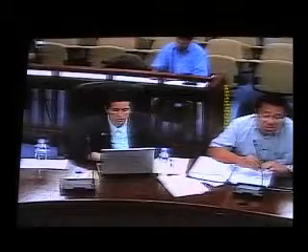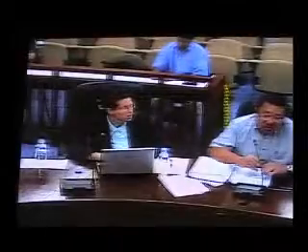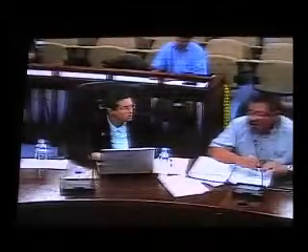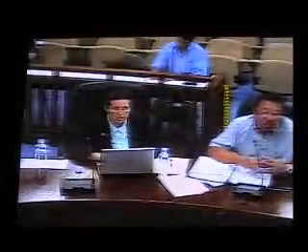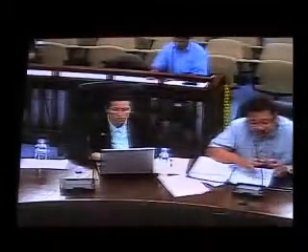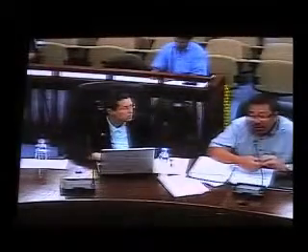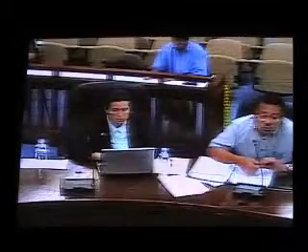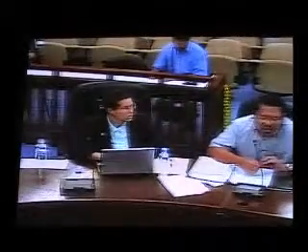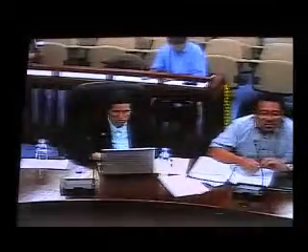The two engines in Tinian are Wartsila engines, 5.5 megawatts each. The efficiency is much lower than Power Plant 1. So is Power Plant 4 and Power Plant 2. They're all below Power Plant 1. So your question is, can the efficiency of the power plant be raised? We expect the efficiency to increase towards the end of next year, 2013, because that is when we're going to replace the radiators through an ARRA grant.